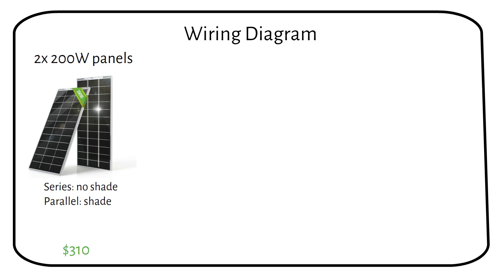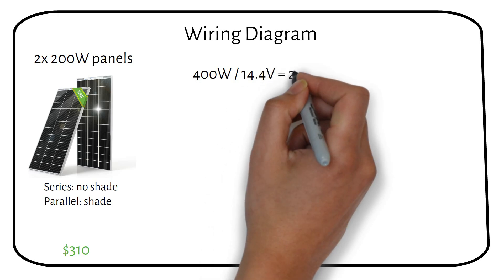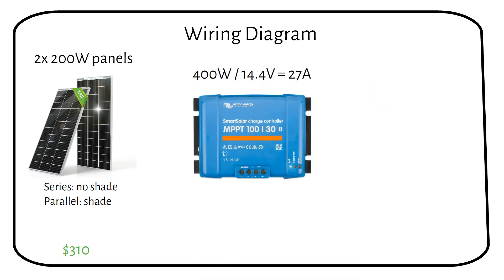To determine the charge controller power requirement, we will use the formula: 400 watts divided by charging voltage equals 27 amps. A 30 amp charge controller will be sufficient.